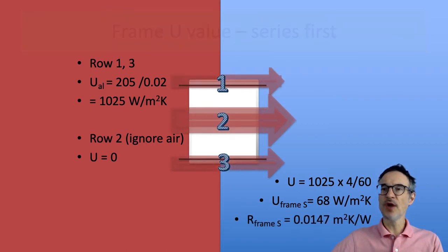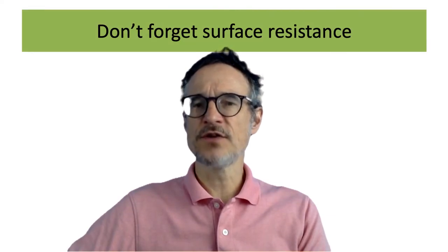These two numbers, the U value calculating this way and the U value calculating that way, there's a big difference between these two numbers. We don't have a very reliable idea of what the number is, but let's just put it somewhere between the two. The other thing as well is don't forget surface resistance.